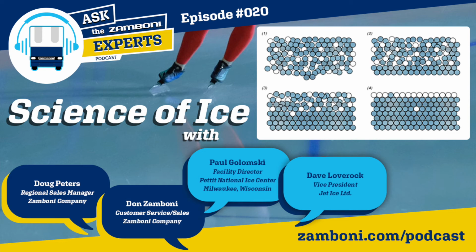So, we started discussing that about 10 years ago. I didn't think we were capturing very much in the wash water stream, and so you had come up with some ideas on what we could try, and so we tried these felt filter bags that are lower micron than what the basket was capturing. And pretty quickly we knew that we were onto something, in that I was getting loads and loads of solids into these felt filter bags that I wasn't getting before in the plastic baskets. So that kind of evolved where we tested them for a few years and really saw an improvement.